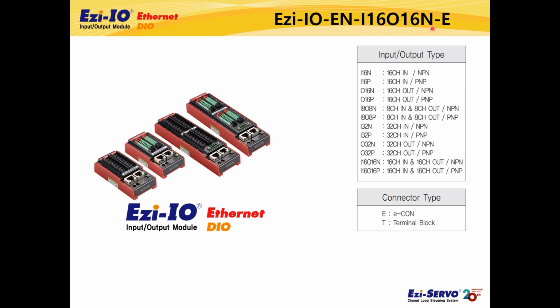I16O16N means an NPN-type product with 16 channels of input and 16 channels of output. E means a product using e-CON-type connectors. There are two options, 16 channels and 32 channels, and input-output alone or mixed selection is possible. For example, the I16N model has 16 input channels, and the O16N model has 16 output channels. An I8O8N model has 8 input channels and 8 output channels.